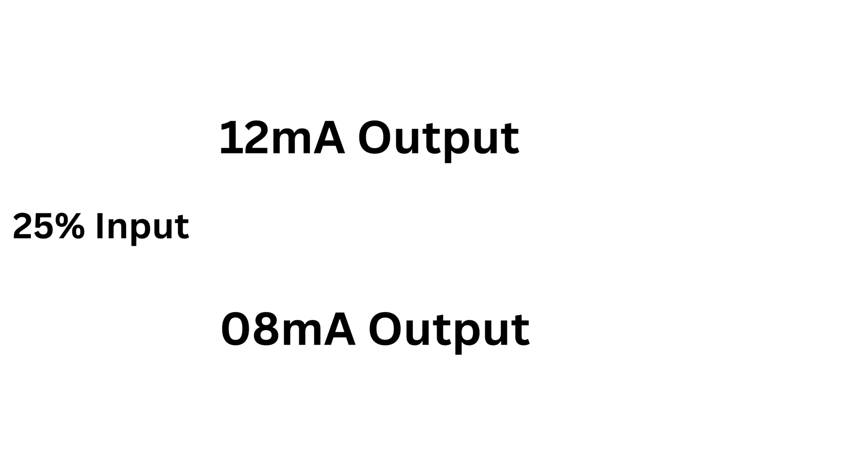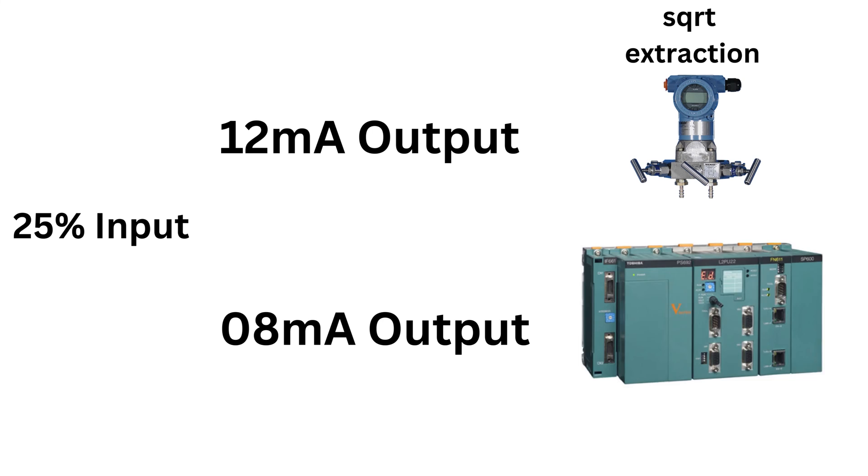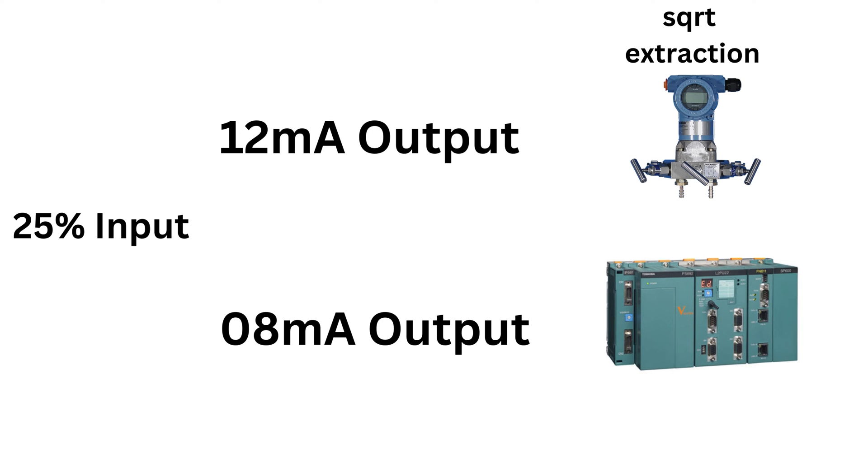A third option is to simulate 25% of the DP range with the pressure calibrator and look at the output in mA of the DP transmitter. If the output is about 12 mA, the square root extraction is performed by the transmitter. If the output is about 8 mA, the square root extraction is performed by the PLC-DCS.